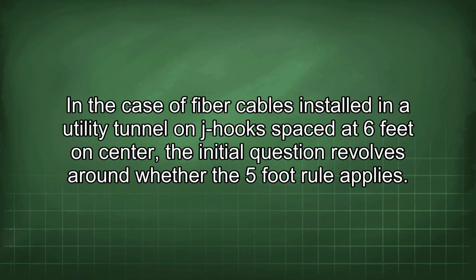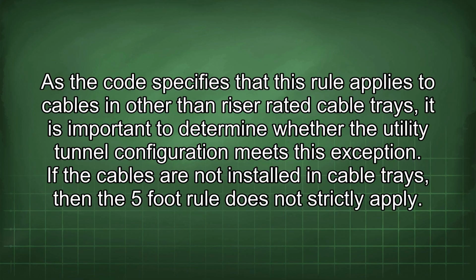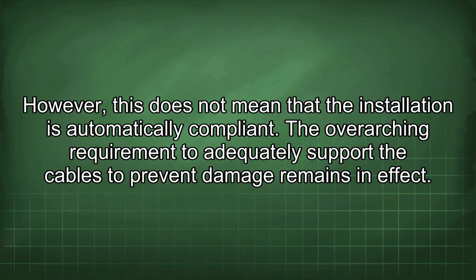In the case of fiber cables installed in a utility tunnel on J-hooks spaced at 6 feet on center, the initial question revolves around whether the 5-foot rule applies. As the code specifies that this rule applies to cables in other than riser-rated cable trays, it is important to determine whether the utility tunnel configuration meets this exception. If the cables are not installed in cable trays, then the 5-foot rule does not strictly apply. However, this does not mean that the installation is automatically compliant. The overarching requirement to adequately support the cables to prevent damage remains in effect.